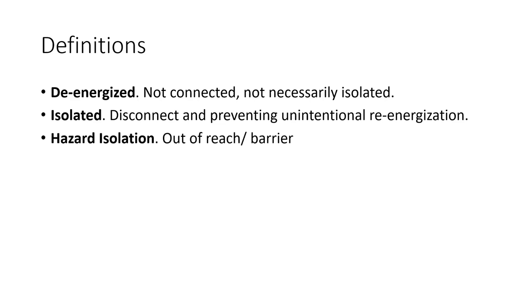It's interesting to note that the hierarchy of controls also mentions hazard isolation, but this is a control measure and it shouldn't be confused with electrical isolation. Hazard isolation is to put something out of reach or put a barrier over it. So electrical isolation is the best form of control because you've eliminated the hazard altogether.